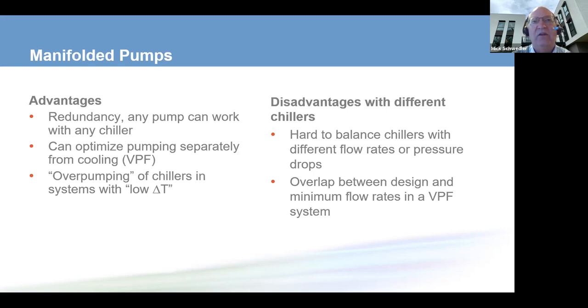There are some disadvantages with manifolding the pumps, particularly with different chillers. And that is if we have different flow rates, the flow has to balance between those two chillers. We might need some balancing valves if we have different flow rates or pressure drops. The second one is even harder. Let's say we have two or three different chiller sizes in a variable primary flow system. Well, when we get up to the design flow rate of the small chiller, we might not be up to the minimum flow rate for the larger chiller.